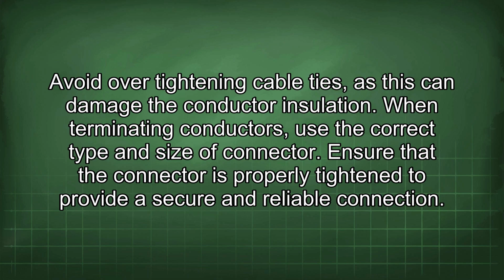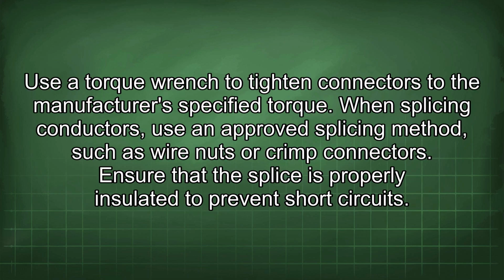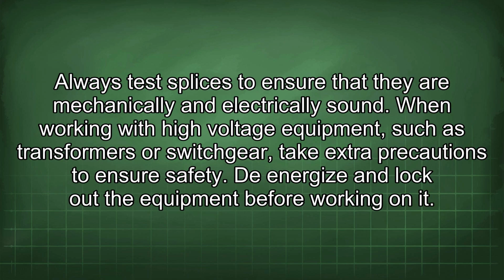When terminating conductors, use the correct type and size of connector. Ensure that the connector is properly tightened to provide a secure and reliable connection. Use a torque wrench to tighten connectors to the manufacturer's specified torque. When splicing conductors, use an approved splicing method, such as wire nuts or crimp connectors. Ensure that the splice is properly insulated to prevent short circuits. Always test splices to ensure that they are mechanically and electrically sound.